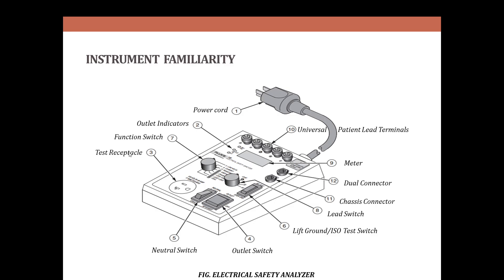Next, the test receptacle supplies power to the devices which are under test. The outlet is powered if the outlet switch is set to normal or reversed and the neutral switch is always closed. The neutral switch permits making leakage current measurements under the open condition, which is required by the UL and IEC.